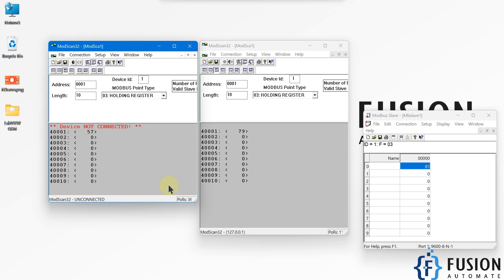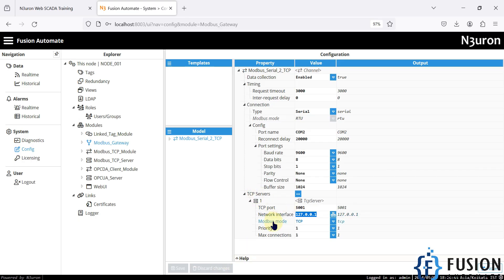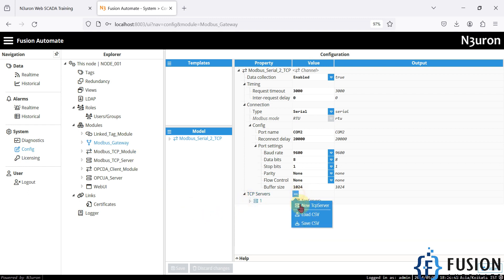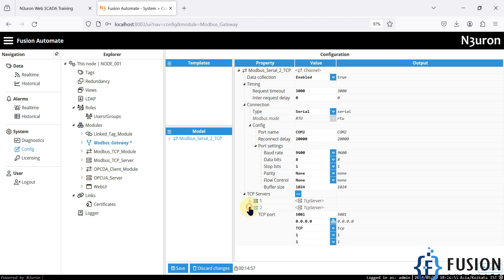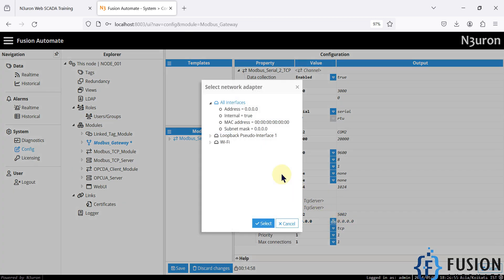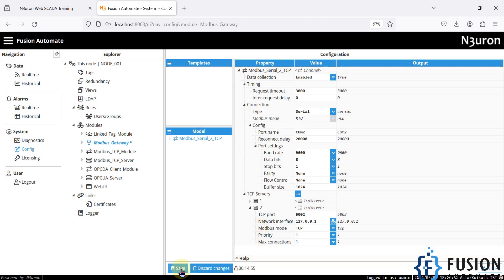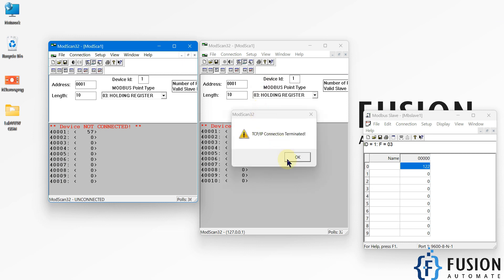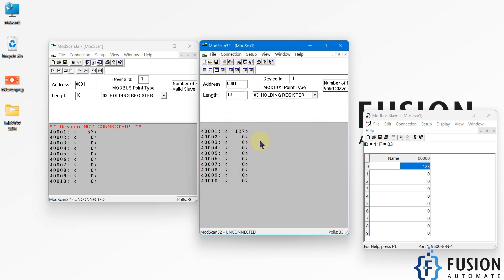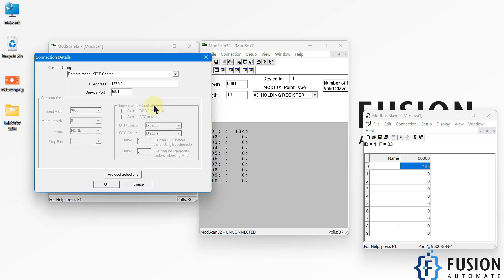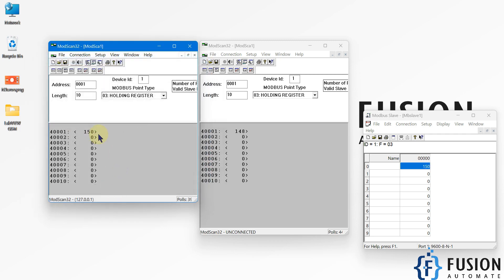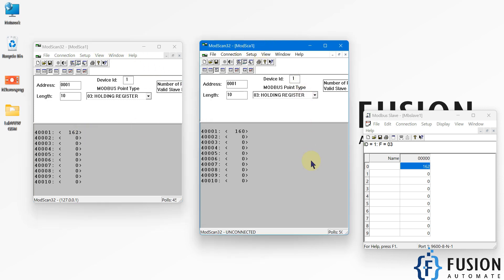Since we want to provide data to multiple applications, I'll create another Modbus TCP server in the Modbus Gateway. This is my second TCP server — I'll use port 5002, network interface localhost, and save. After the module restarts I connect it. In the second ModScan instance I now use port 5002 instead of 5001, and we have data in this second instance as well. These two ModScan instances act as two individual applications, each requiring a separate Modbus TCP server.